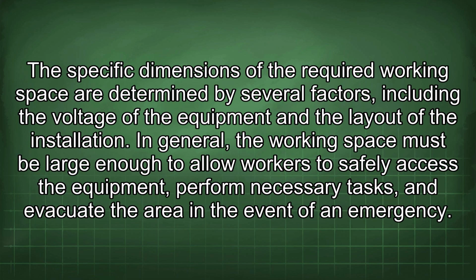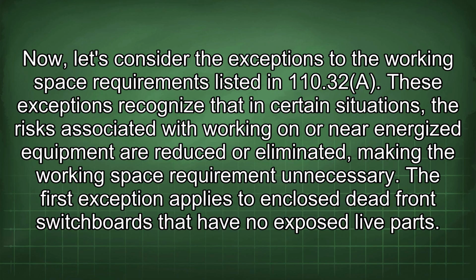The specific dimensions of the required working space are determined by several factors, including the voltage of the equipment and the layout of the installation. In general, the working space must be large enough to allow workers to safely access the equipment, perform necessary tasks, and evacuate the area in the event of an emergency. Now, let's consider the exceptions to the working space requirements listed in 110.32a. These exceptions recognize that in certain situations, the risks associated with working on or near energized equipment are reduced or eliminated, making the working space requirement unnecessary.